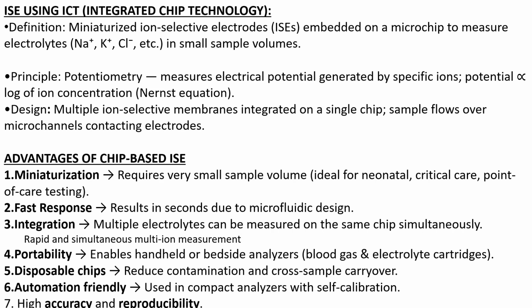There are multiple ion selective membranes integrated on a single chip. The sample flows over microchannels contacting the electrodes. The advantage of the chip-based ISE is miniaturization, so it requires only a very small volume of sample. The fast response: the results arrive in seconds due to the microfluidic design. Integration: multiple electrolytes can be measured on the same chip simultaneously. So rapid and simultaneous multi-ion measurement is possible.